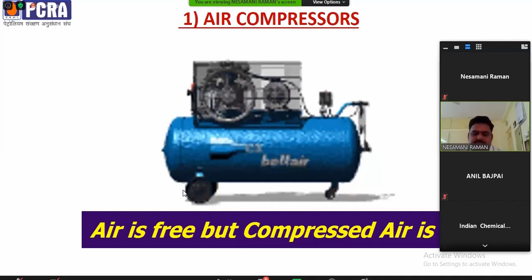If you give 100 kilowatt of power as an input to the compressor, 80 percent of the input power will be lost in the form of heat of compression. 5% will be lost in mechanical losses. So 15% will be the output in the form of pressurized air. But even that is being wasted, almost 50% is wasted in the form of leakages. So at the end of the day, only 7.5 kilowatt of the input power we will be getting in the form of compressed air.